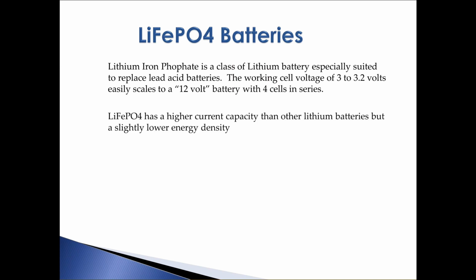The LiFePO4 has a higher current capacity than other lithium batteries in terms of its peak output, but it does have a slightly lower energy density, about 14% lower than the best competitor. It also has a very low self-discharge rate, so you can leave a battery like this on the shelf for a year and still come back and have probably 70% or more of the usable energy still in the battery. At that point, a lead acid battery would probably be completely depleted.